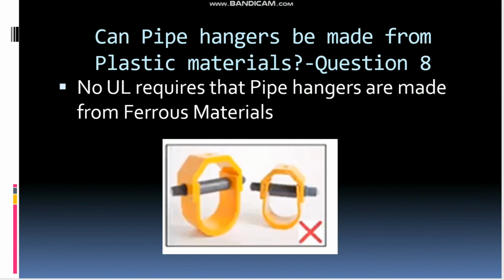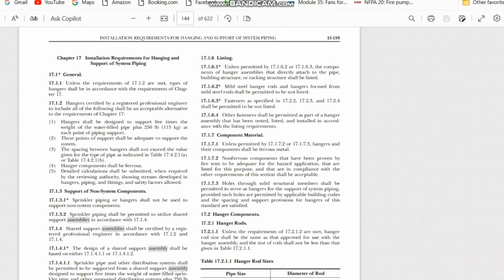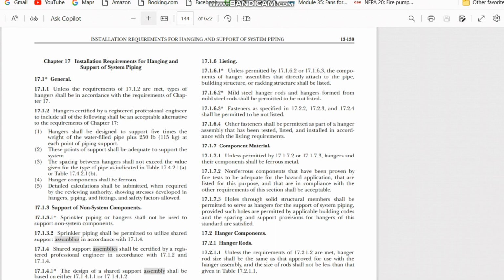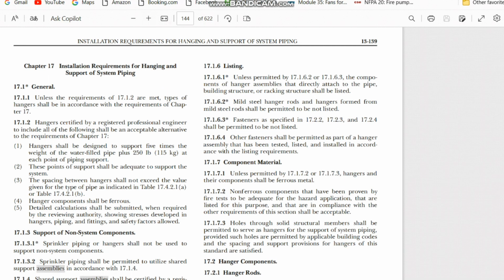The question here is, can we use pipe hangers made from plastic materials? Normally what we see here is non-plastic material, like non-ferrous or ferrous material only. So can we make pipe hangers from plastic? That is the question. As per UL, it is not approved to use pipe hangers from plastic material. But if you see NFPA 17.1.7.2, non-ferrous components can be used if they are properly tested, like fire testing, and properly listed.